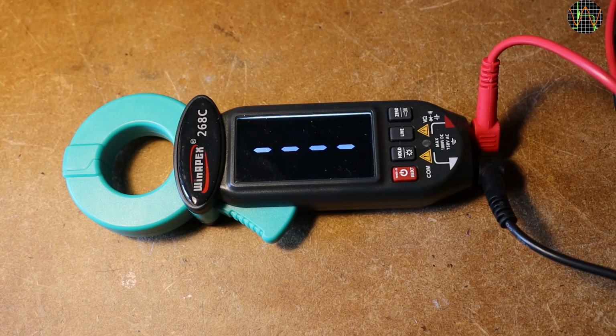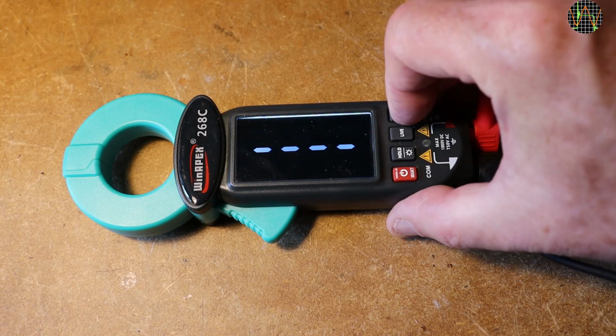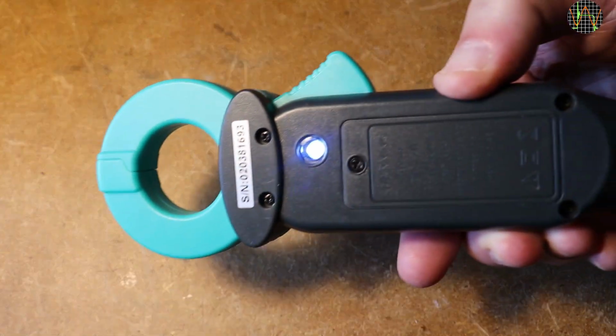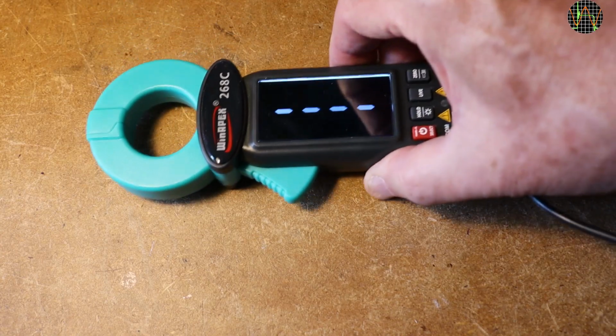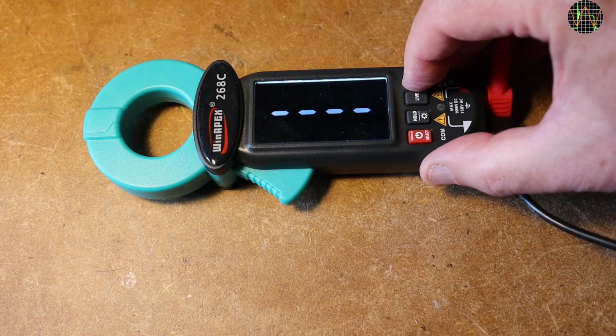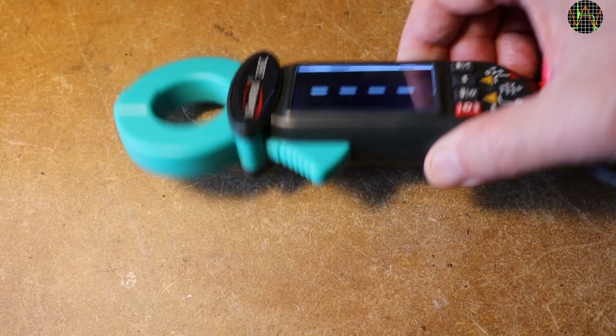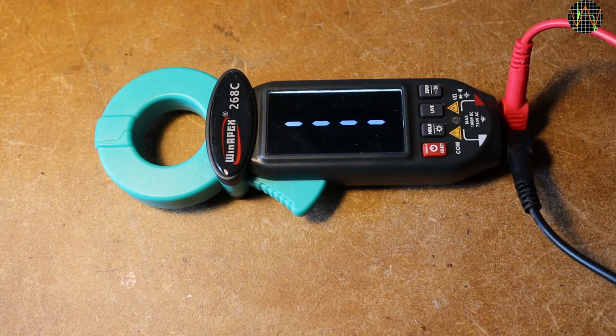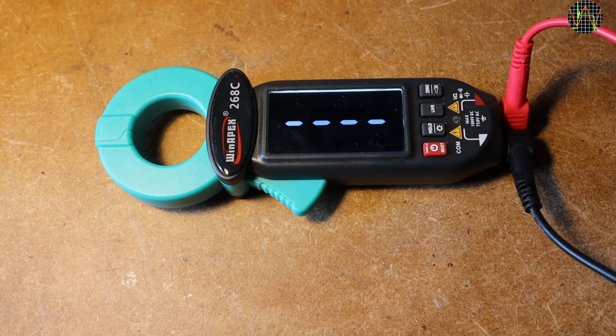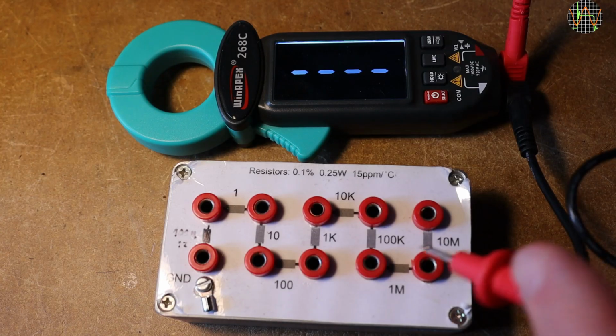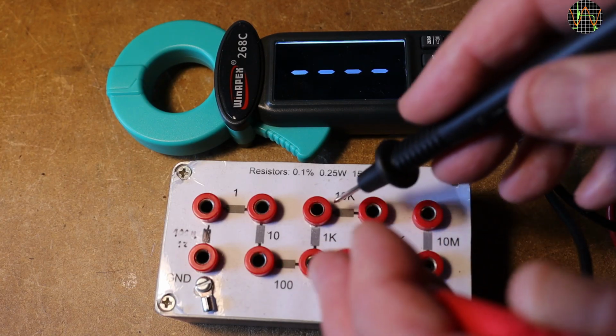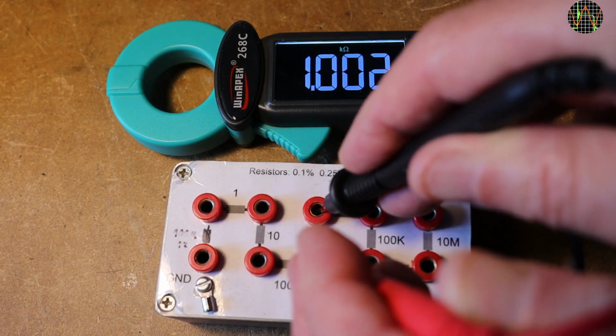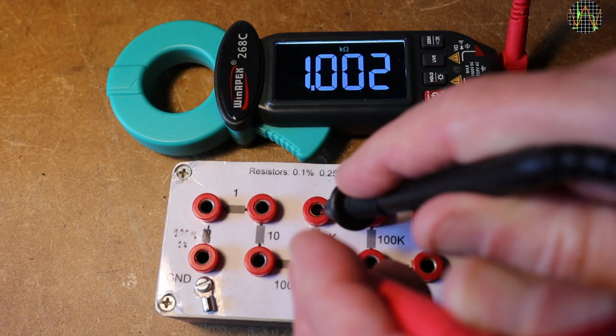Similarly, the zero function is not implemented in the 268C model, but the torch function does work, although the light is rather dim and comes out at the bottom, which doesn't strike me as a very useful position for a torch light. Lastly, the hold button does the usual thing, and a long press allows you to dim the display should you so wish. I'm not going through all the functions, they all work as you would expect, just a few highlights. In auto mode, the meter is very quick in deciding the ohms and selecting the right range. This is quite impressive. I have seen much worse.